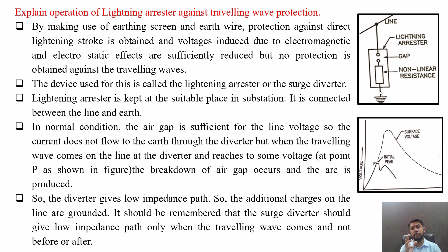State the essential characteristics of surge diverters. So there are several characteristics of surge diverters. The following are essential or needful characteristics for good surge diverters, like no current should flow through the surge diverter in the normal healthy condition. Easy path to earth should be given by the diverter when the overvoltage comes. The diverter should be capable of withstanding discharge for some period of time after the discharging of current itself. The secondary transient should not be produced during this operation. The surge diverter should work normally as before after the transient is suppressed. Means once the transient part is over or suppressed, the surge diverter should work normally as before.